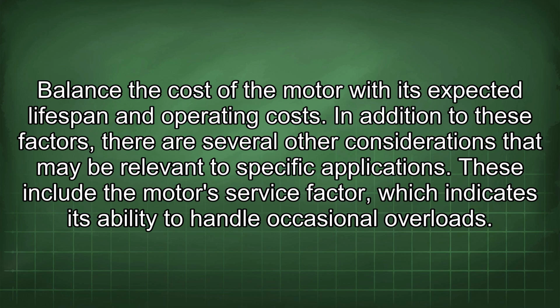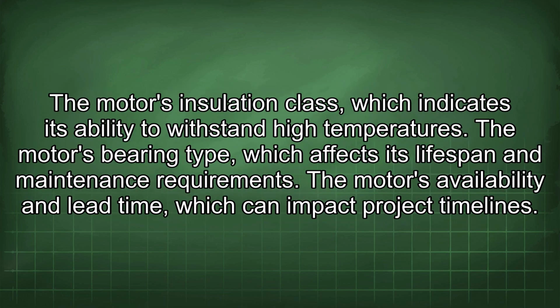In addition to these factors, there are several other considerations that may be relevant to specific applications. These include the motor's service factor, which indicates its ability to handle occasional overloads. The motor's insulation class, which indicates its ability to withstand high temperatures. The motor's bearing type, which affects its lifespan and maintenance requirements. The motor's availability and lead time, which can impact project timelines.